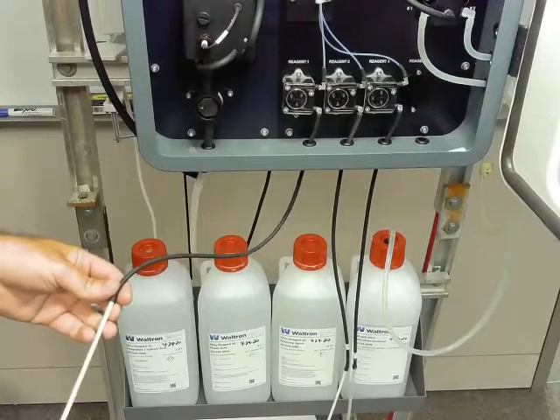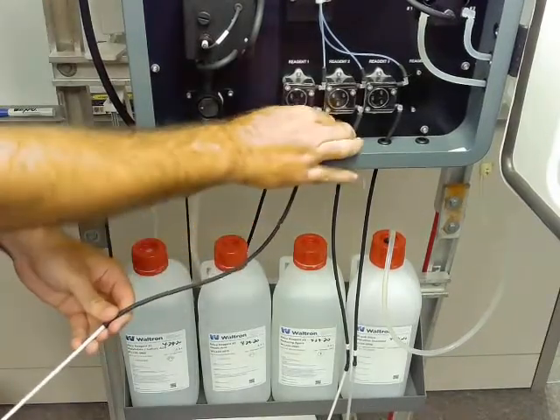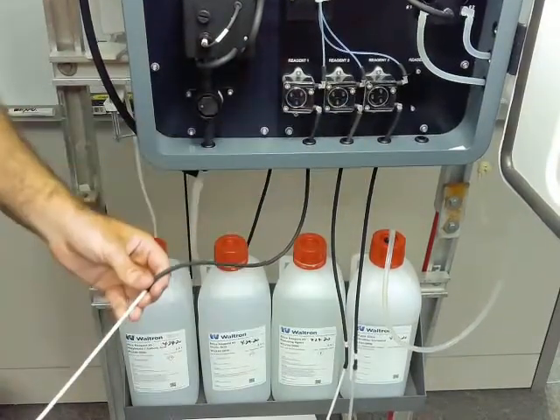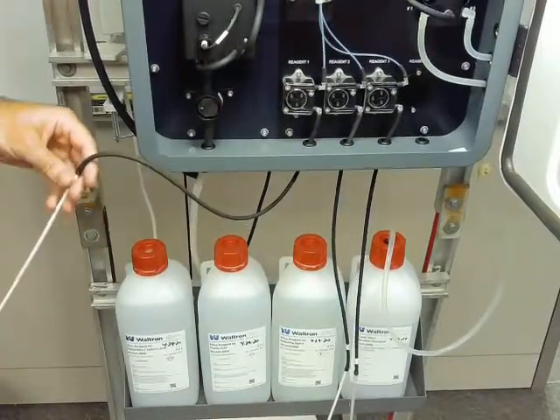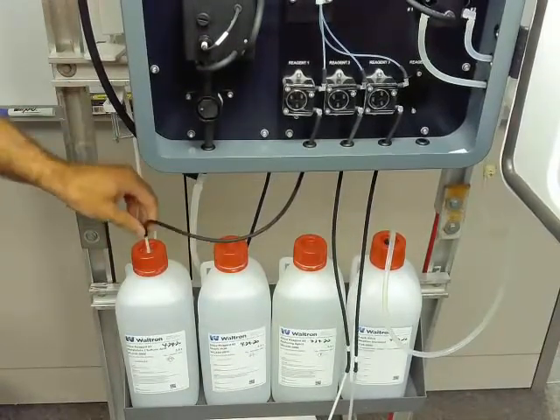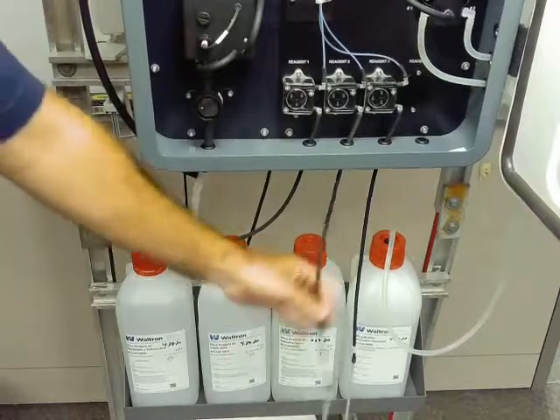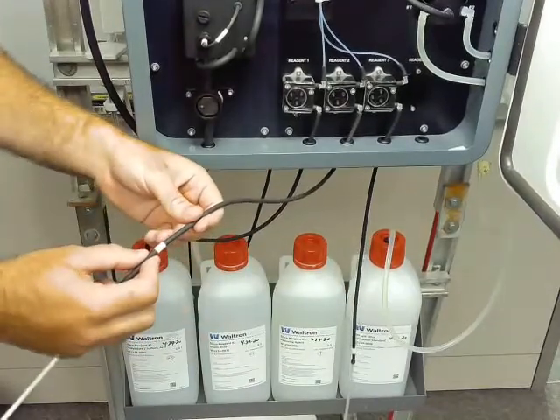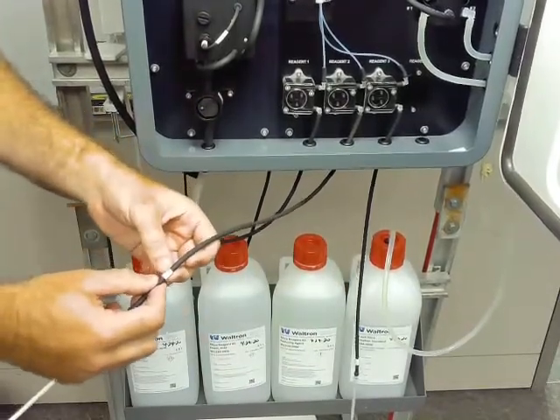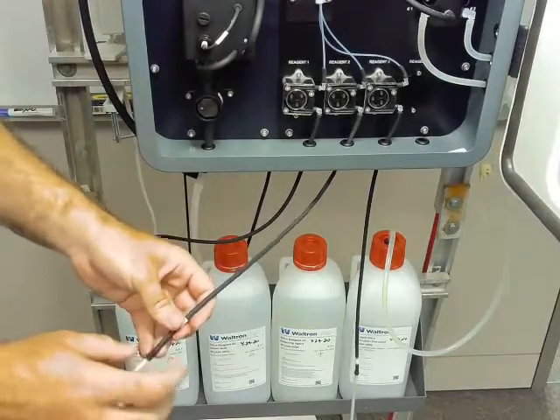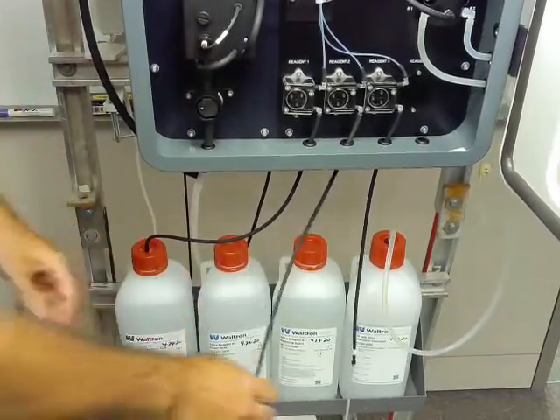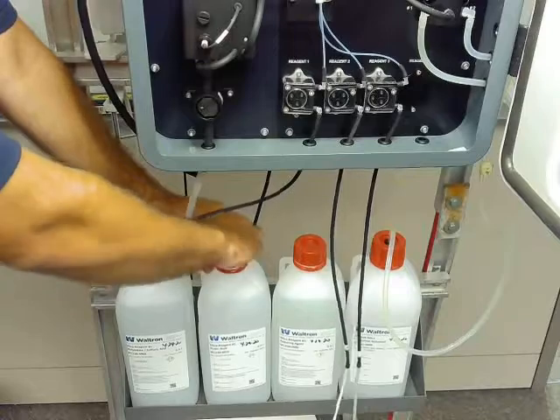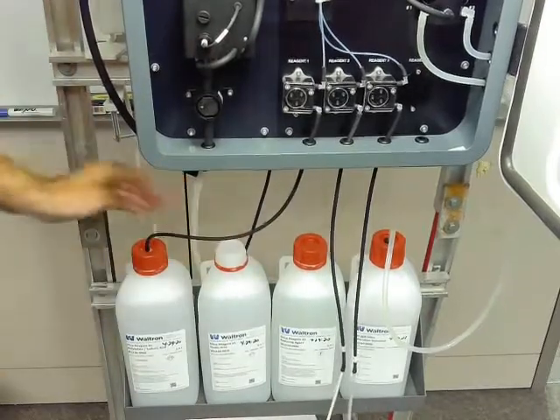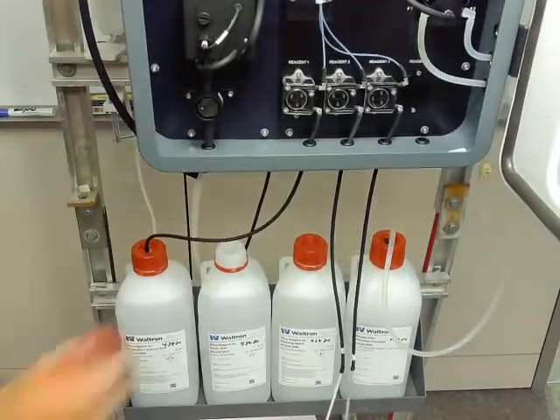So on the bottom of the analyzer, you have your reagent straws, which connect to the bottom of our reagent pumps. Again, it's as simple as putting that straw into the bottle. Usually they're numbered, so for instance, this one says R2 on it here. You probably can't see it in the video, but line up R2 with the second reagent and the second reagent pump, and so forth for all three reagents.